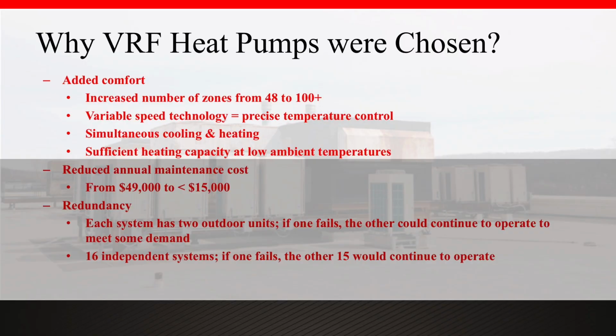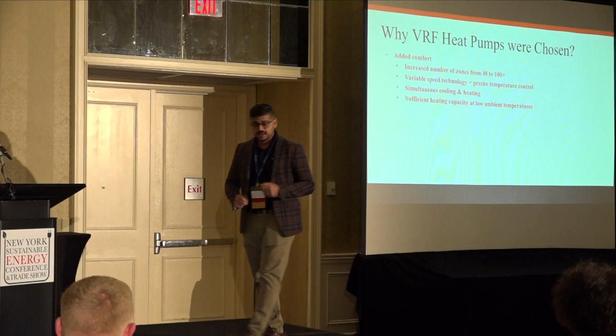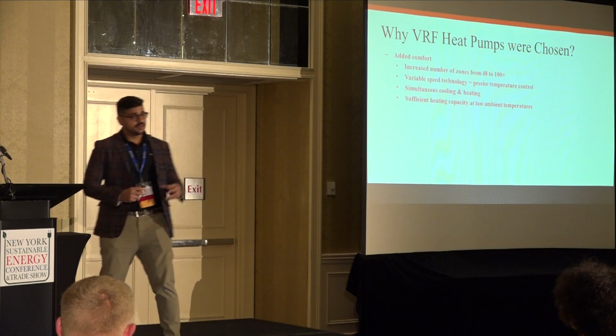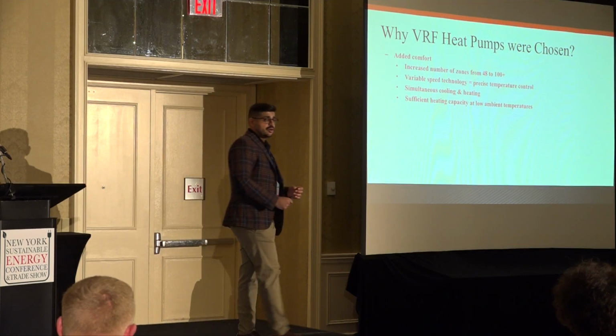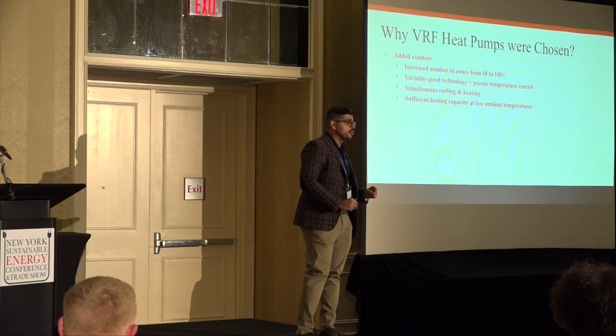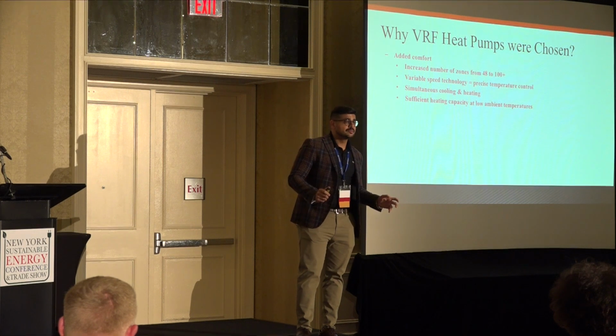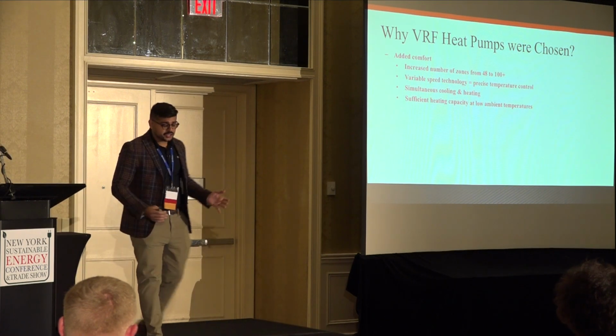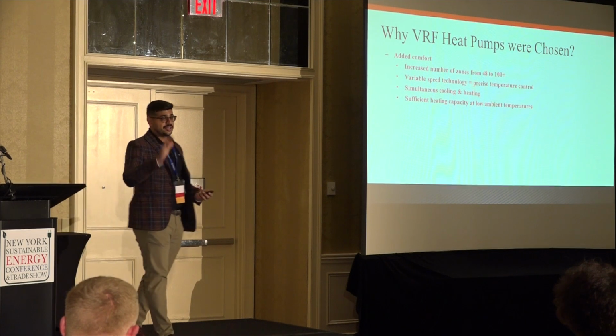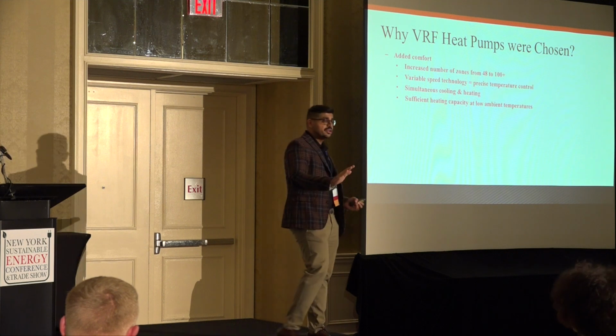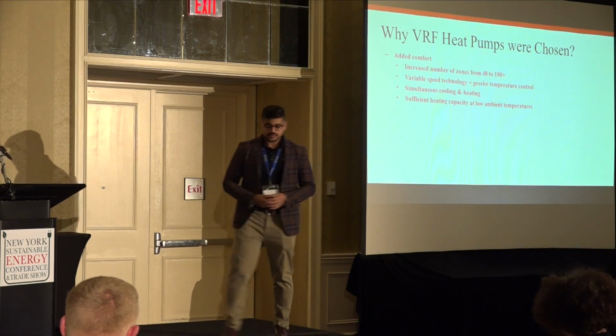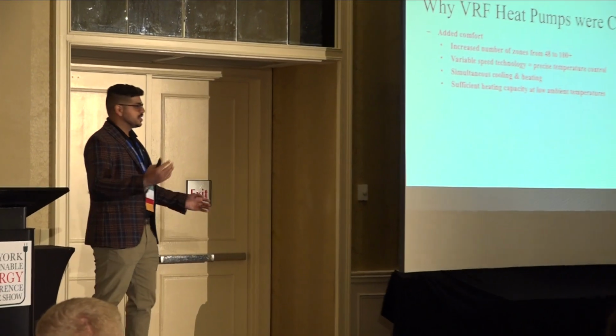Well, a big one was added comfort. Okay? Right now, or before the VRF was installed, there were 48 zones in this building. With the super amazing zoning capability of VRF systems, we're able to take that to over 100. Okay, so now before, that occupant that could not control the temperature in their space can now do it. It's a big win, right? Also, variable speed technology equals really precise temperature control, kind of like the accelerator in your car. Okay, the amount of pressure you put in is how fast your car is going to go. Okay, also simultaneous cooling and heating. In the same system, one zone can give you heating while the other can give you cooling. And then also a really big one is it's able to output sufficient heating capacity at low ambient temperatures?